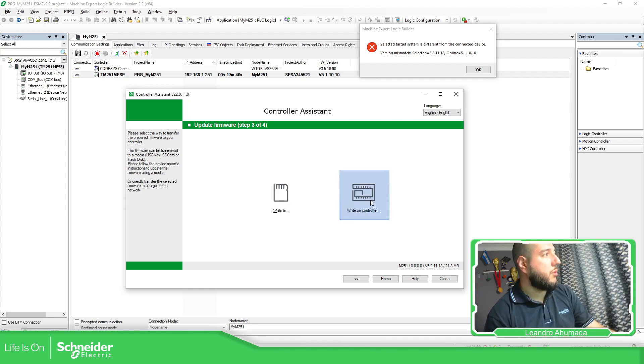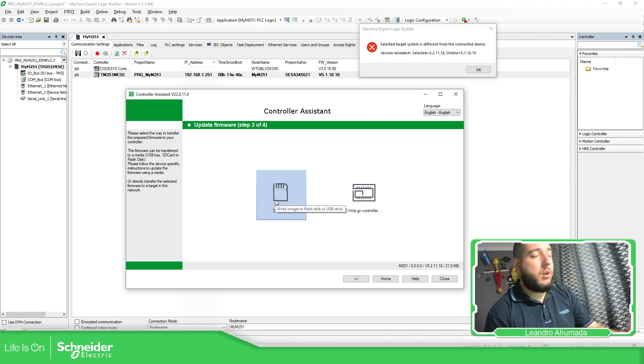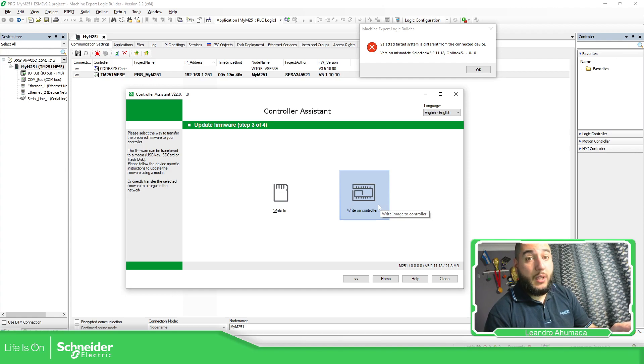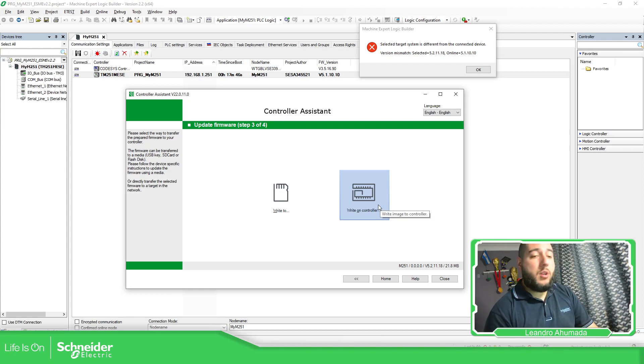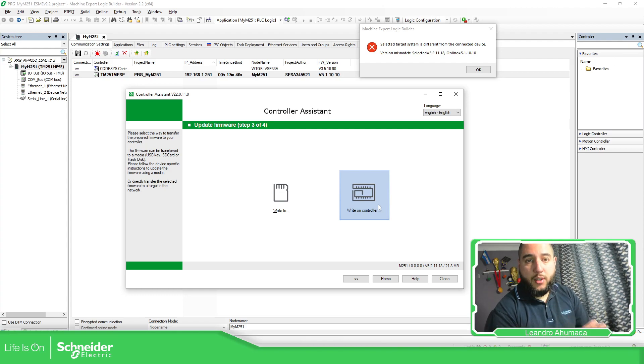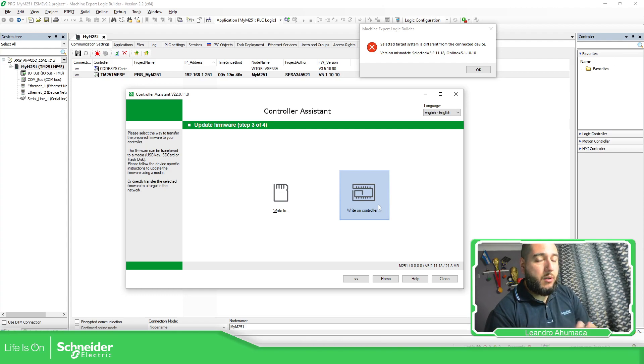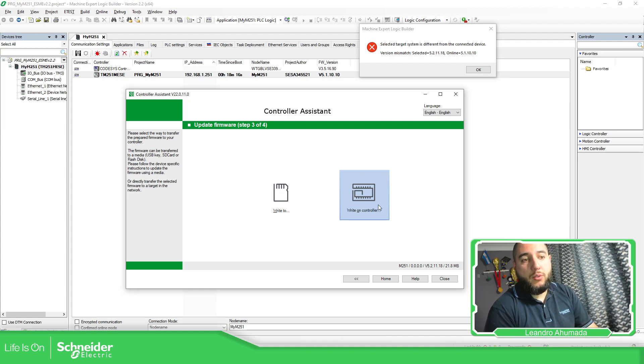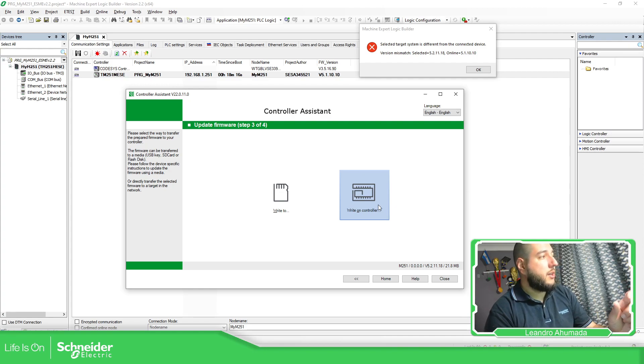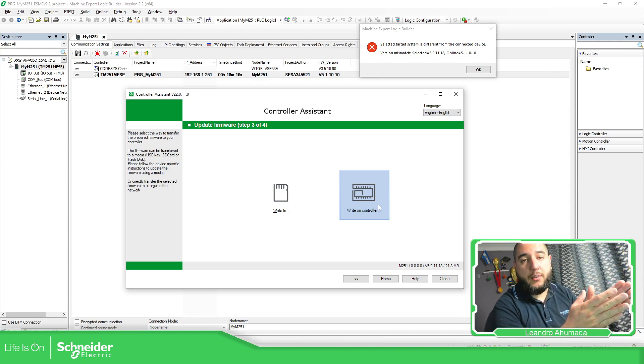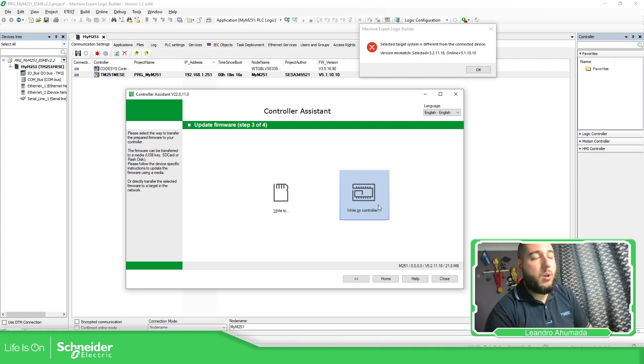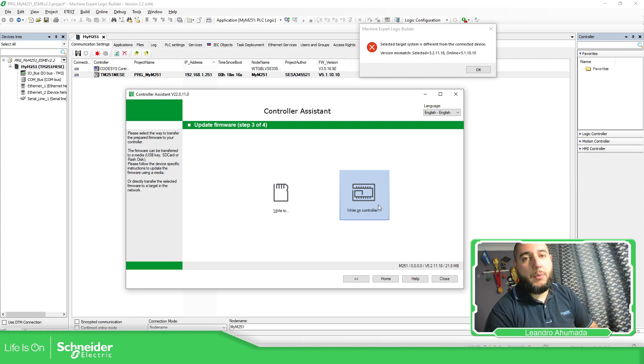And here you have the possibility to use an SD card or directly to the controller. Now, if you don't know the password, then the best option is to use the SD card. So we will reset all the credentials that you have on the controller. And that probably will be mandatory if you're using some machine, because probably you need to check. Maybe the PLC has a password and in some machine, we don't have that as credentials. So probably using SD card is going to be the easiest.